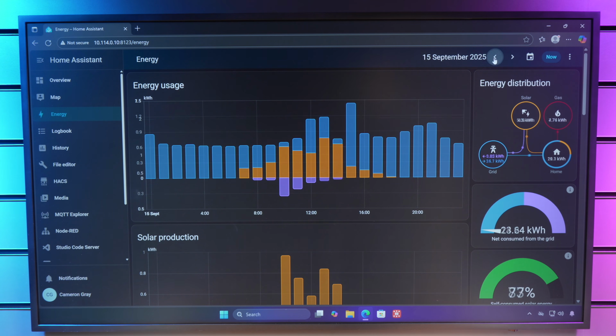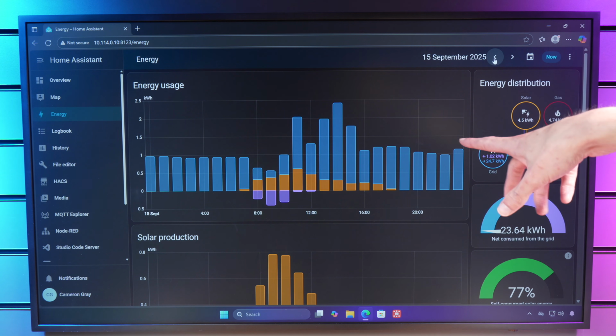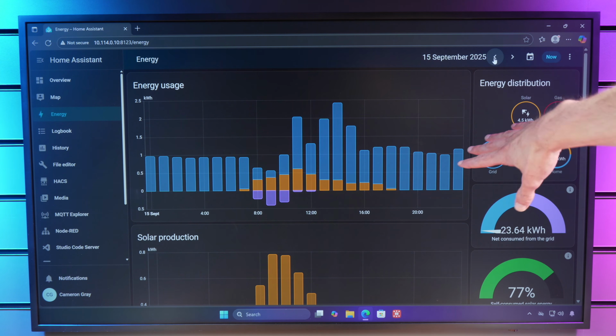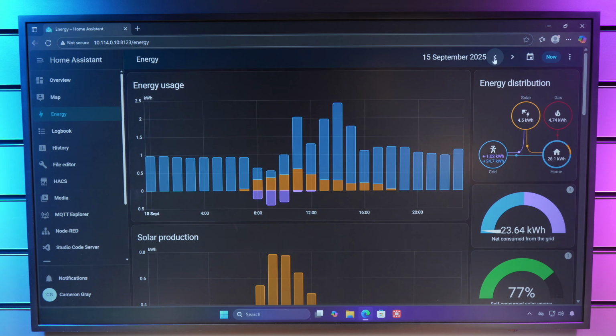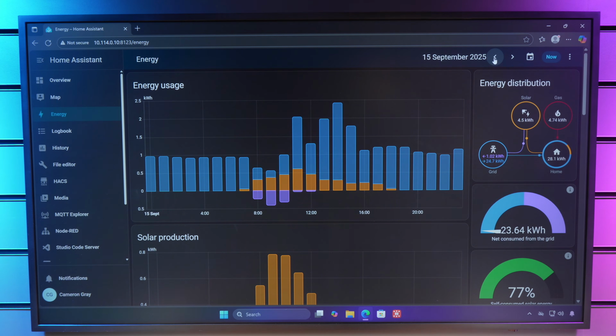However, if we go back to the previous day, this was before I moved those CTs. I think I moved them round about midnight, so right towards the end of the day. So this is back when the CTs were on individual circuits and we're measuring just the same power level, but with the CTs separated out, where we're having that error.